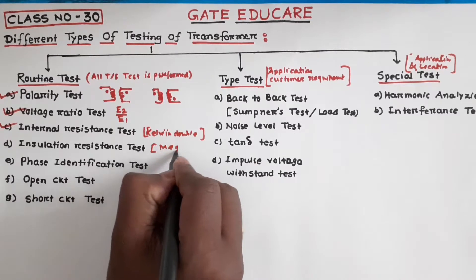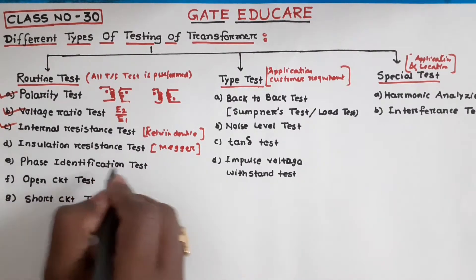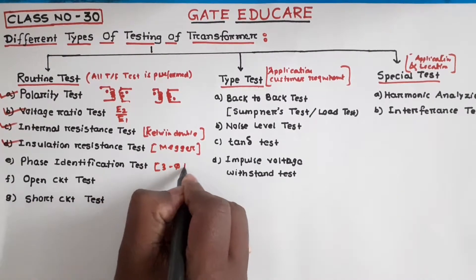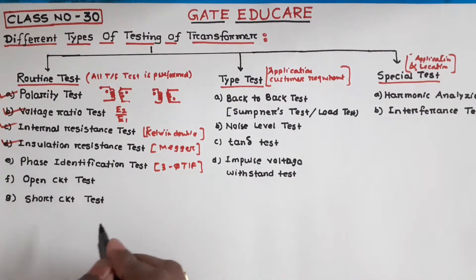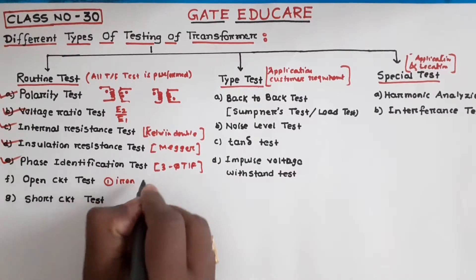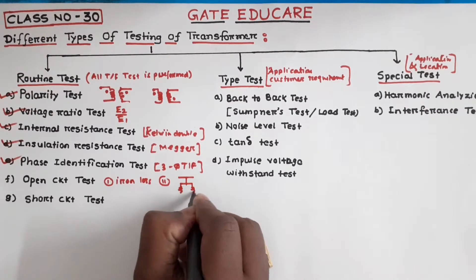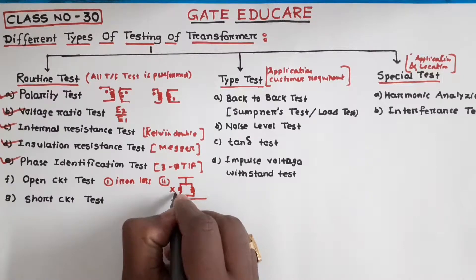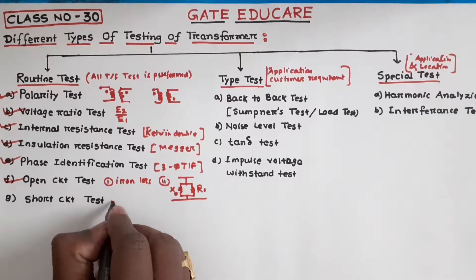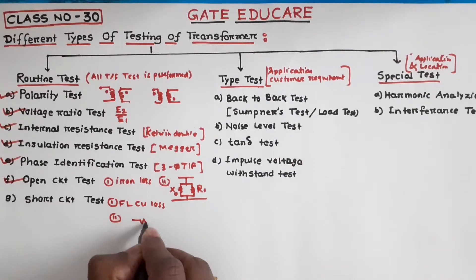Next, measurement of insulation resistance test. With the help of a Megger test, the insulation between the windings is measured. Phase identification test: the phase identification test is generally performed on a three-phase transformer to determine the phase sequence — whether it is RYB or RBY. Open circuit test: with the help of the open circuit test, mainly iron loss and shunt branch parameters R0 and X0 are measured.